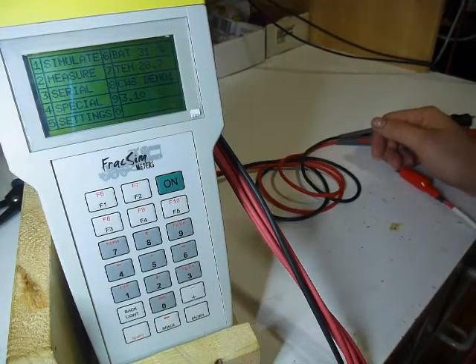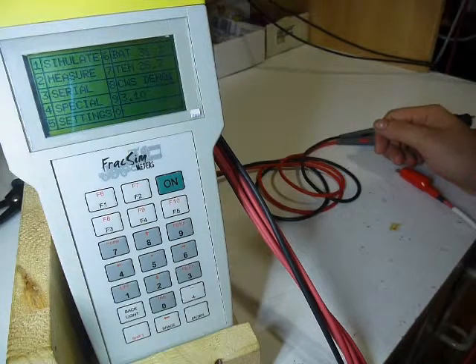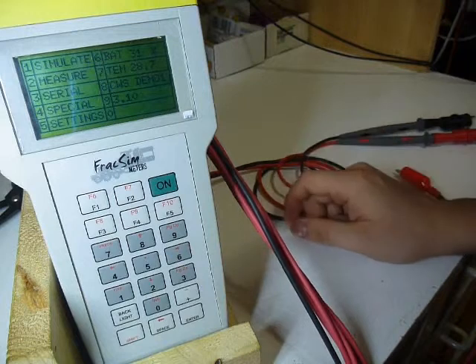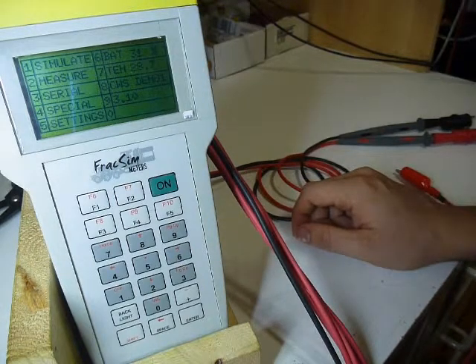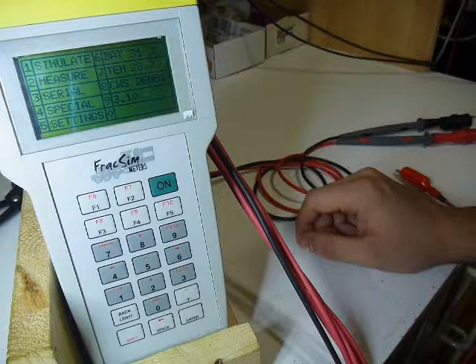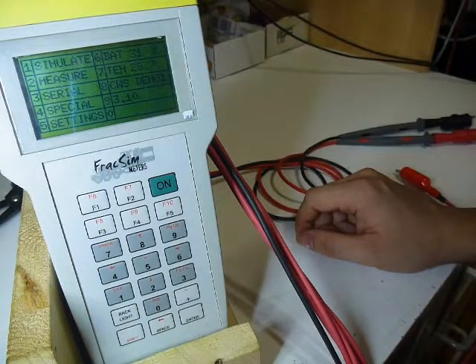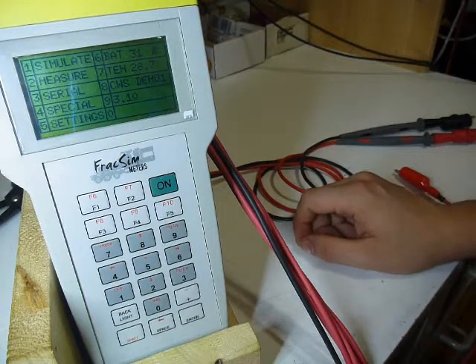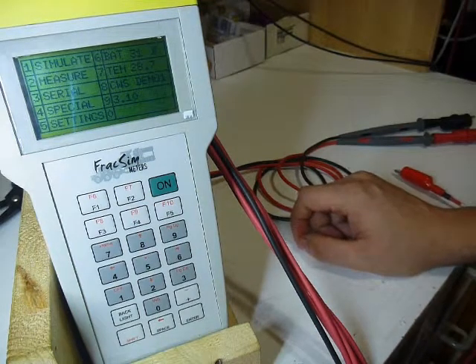It's not recommended, to avoid voiding the warranty, but it is relatively waterproof compared to any other conventional meter or process calibrator you'd find. Now I should go over the limitations too, not just talk about how good everything is. It's not rated for any high voltage, so it will not measure AC voltage, and you could end up damaging the meter if you try putting high voltage or high current into it. The current measurement is only good for 4-20 milliamp stuff.